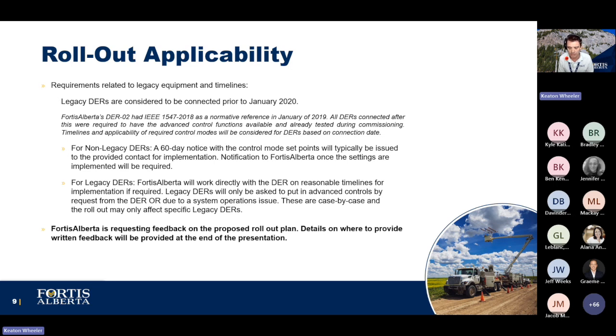I will include here FortisAlberta's DER2, which is our interconnection standard associated to these. We had IEEE 1547/2018 as a normative reference in January of 2019, so we've given an extra year. All DERs connected after this were required to have the advanced control functions available and already tested during commissioning.